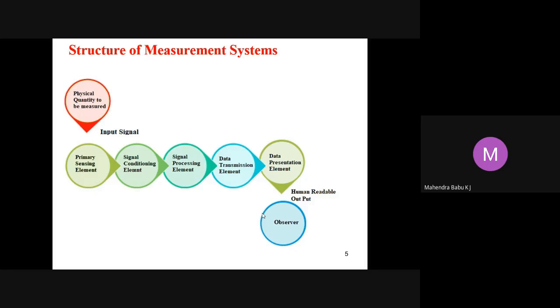If there is more than one sensing element in a system, the element in contact with the process is termed the primary sensing element. Otherwise, it is a secondary sensing element. And the second element is the signal conditioning element. This will take the output of the sensing element and convert it into a form more suitable for further processing, usually a DC voltage, DC current, or a frequency signal.